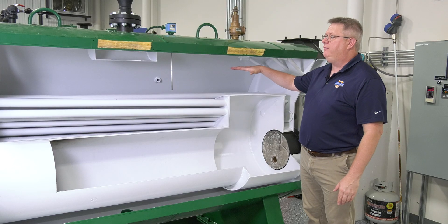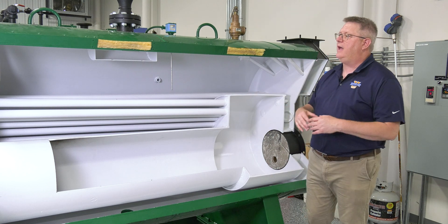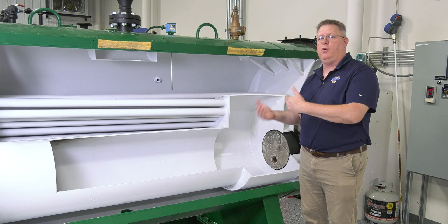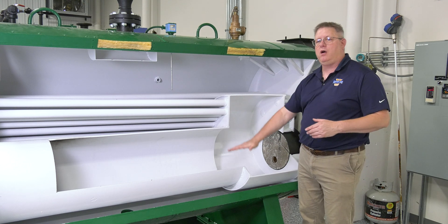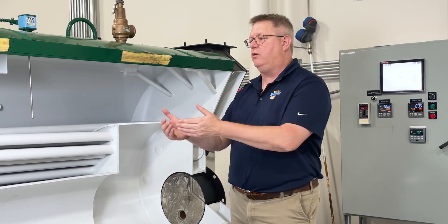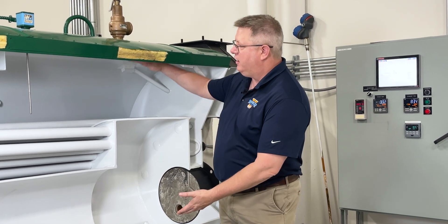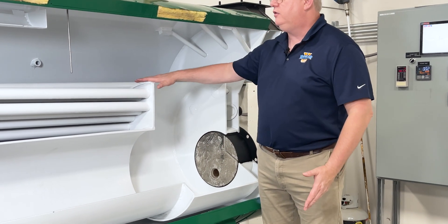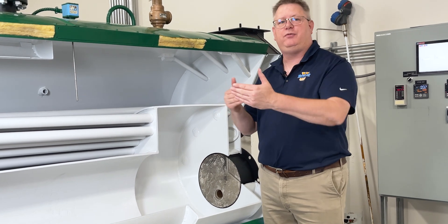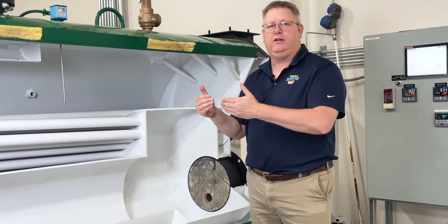But in a steam boiler, if we've got the boiler up to 140 degrees, what we have to keep in mind is the fundamental difference between a steam boiler and a hot water boiler — and that main difference is a hot water boiler is flooded. So if we've got a boiler at 140 degrees and we're operating at high fire, all of the components of the pressure vessel from the shell to the tubes to the top of the shell are the same temperature. So there's not a temperature differential that causes pushing and pulling on the heat exchanger.